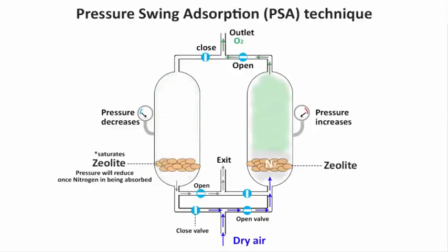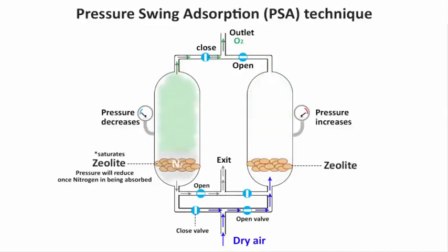This process guarantees a continuous flow of oxygen — you don't have to wait for one tank to become empty before starting the cycle again. This cycle is repeated under an electronic control system to produce high purity and stable oxygen continuously. It is a cost-efficient process offering the best industrial oxygen price and uninterrupted supply. This technology can produce oxygen with an adjustable purity between 90 and 95%, which is ideal for the healthcare industry.